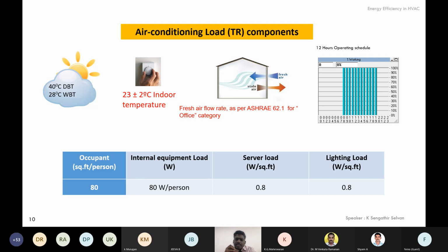As was suggested, occupant clothing also has a major impact in setting temperatures. If we are normally clothed with cotton clothes, our body will still feel comfortable at 25 degrees, and every 1 degree reduction in the HVAC plant actually increases energy consumption by 2%. So we need to be very careful in selecting the indoor temperature.